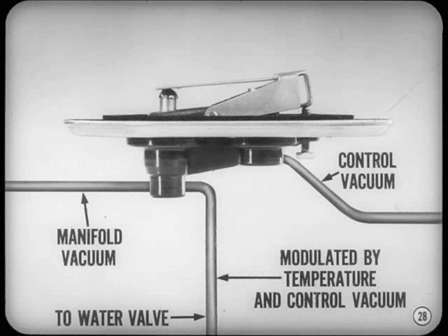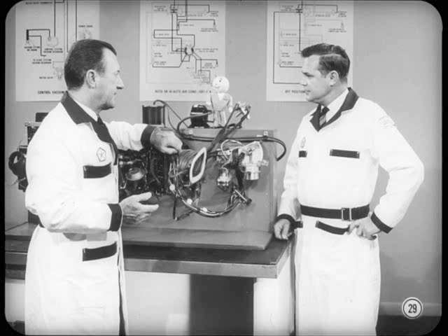At the same time, control vacuum is also acting on the vacuum regulator. As a result, manifold vacuum is modulated by both discharge air temperature and control vacuum before it reaches the water valve. I think you ought to review what we've covered so far, Bob, using the diagrams in the reference book. They show the basic electrical sensing circuit as well as the control vacuum circuit.